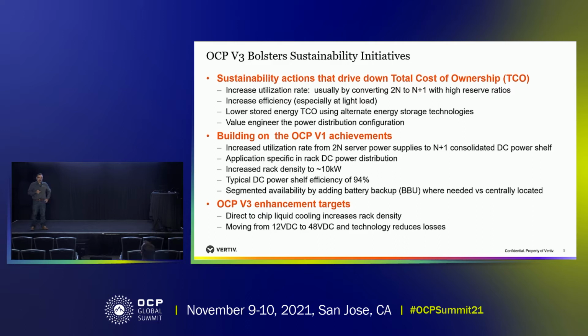The other big change in V3 will be the move from 12 volts to 48 volts. With the higher voltage, you're going to get less losses, again focusing on reducing losses in the power distribution system. So if you add the combination of liquid cooling and the reduction in losses of the power system, you're going to see some nice improvements as you move towards a more dense solution with the V3 design.